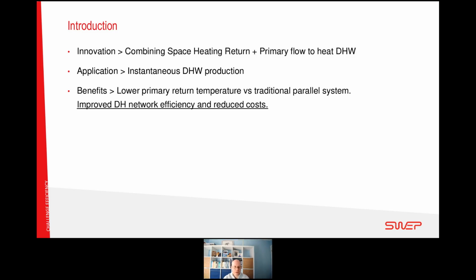The application is quite specific. It's centralized domestic hot water production. So we are talking substations here rather than individual HIUs. So it would be one substation, perhaps serving multiple floors or one floor, but this is the application. And the benefits are, compared with a parallel system, we get much lower primary return temperatures, which is really the holy grail at the moment with heat networks. Constant drive for efficiency, benefiting the end users as well as the system operators. So we're going to look at that in a little bit more detail.